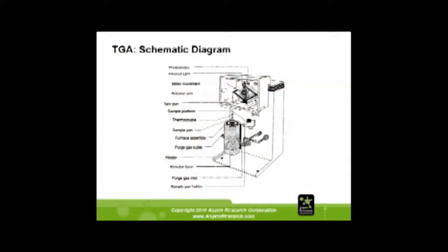Here's a schematic. This is a balance up here. This is purged with nitrogen all the time. Remember, decomposition products come up this direction and it all moves down this way. There's a wire that holds the pan right there that holds on to the sample. This little mechanism over here brings the pan over and hangs it around the wire. The pan is sitting right there and the oven comes up. Gas goes in this way and out this way — your purge gas, whatever you're using.